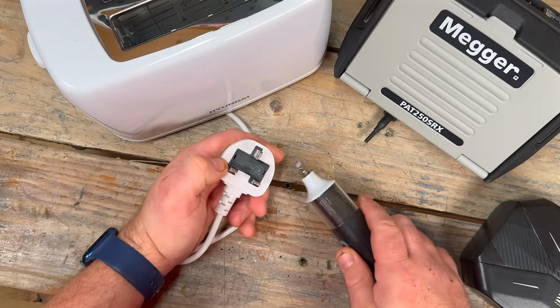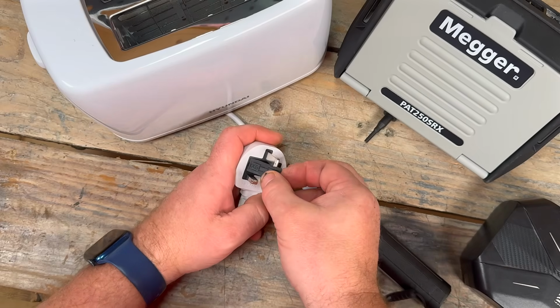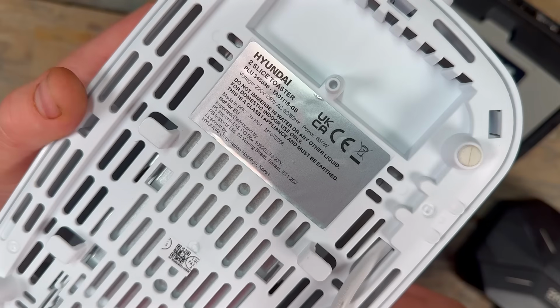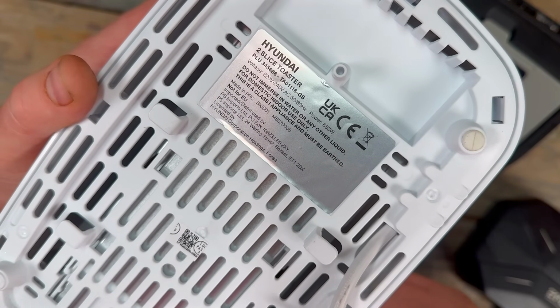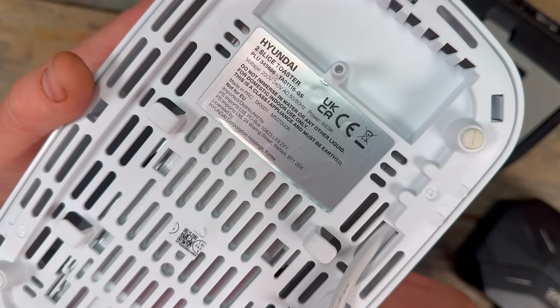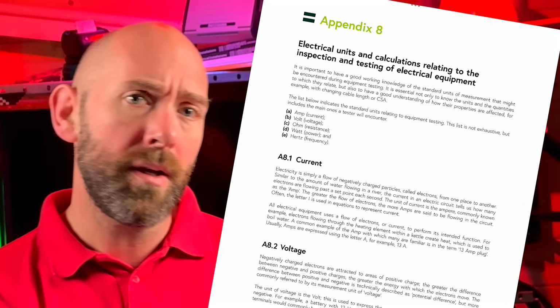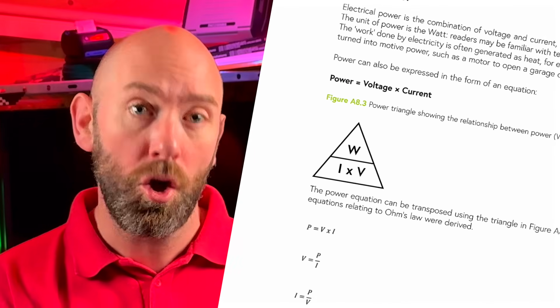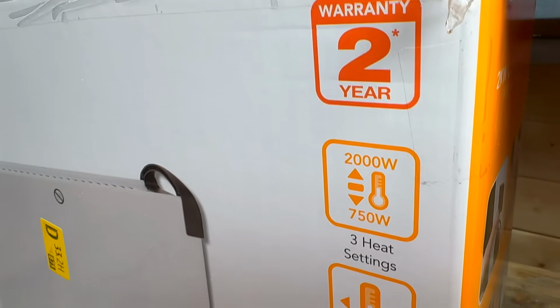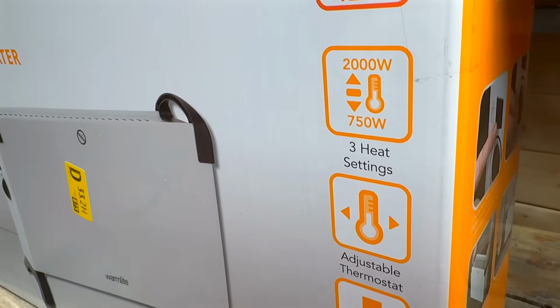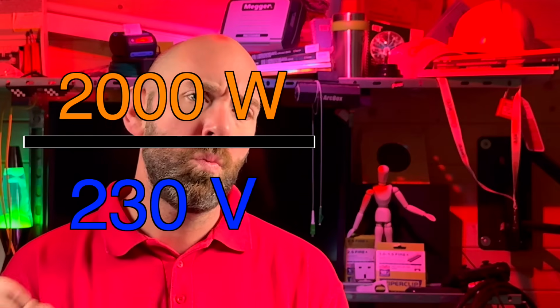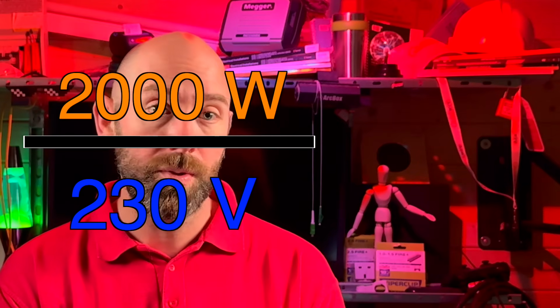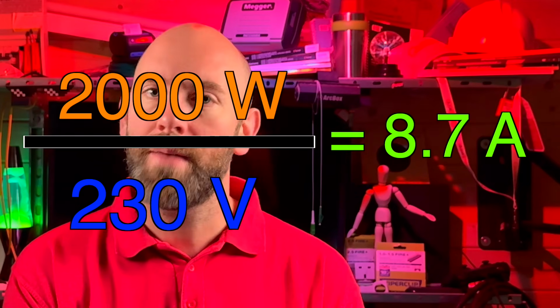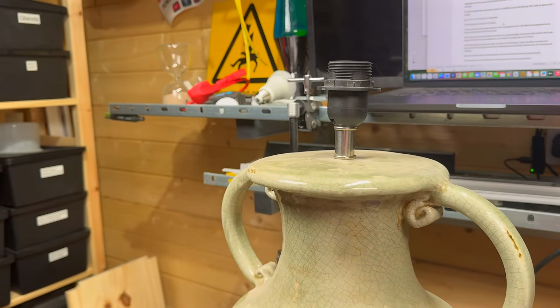The fuse needs to be checked to ensure it's the correct fuse for the appliance. This will normally be written somewhere, however, if not, we can calculate the current of the appliance to ensure the correct fuse is fitted. Appendix 8 of the Code of Practice outlines the power triangle for calculating current. Let's take this heater. The maximum output is 2000 watts or 2 kilowatts. If we divide 2000 watts by 230 volts, that gives us a current of 8.7 amps. So a 10 or 13 amp fuse is required. This lamp has a fuse of 13 amps.